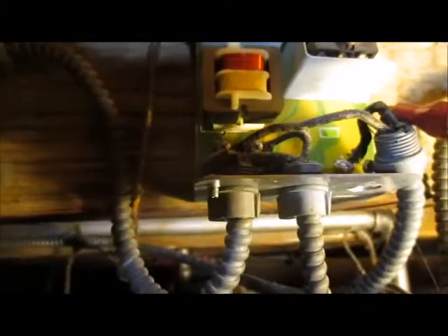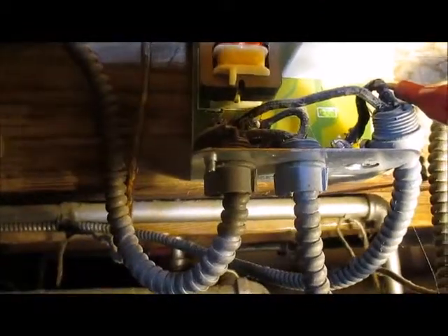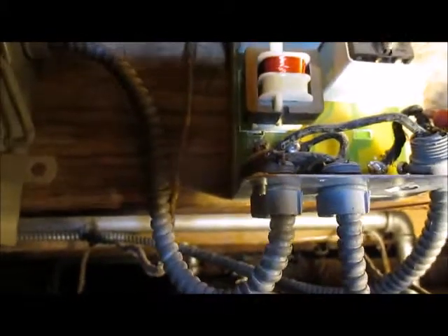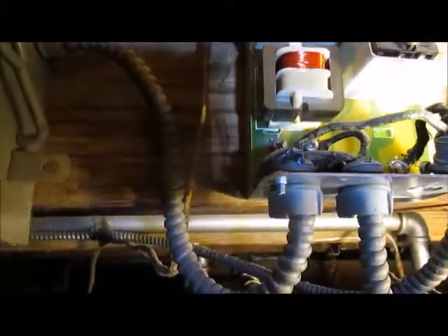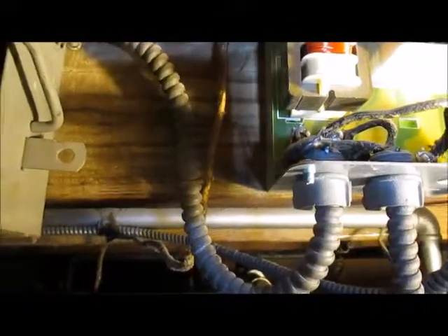When you turn this back on, there's power back to it right now. So I turned the temperature up, waiting for the boiler to go on to show you that this right here is the line to the pump. If this isn't going on, that means there's no power going to it, and this is the circuit that turns the pump on right here.